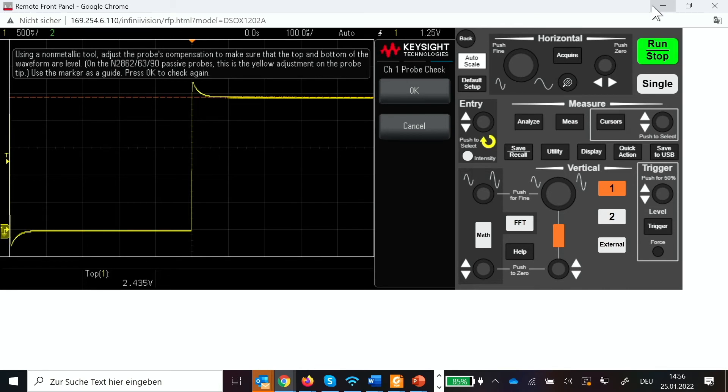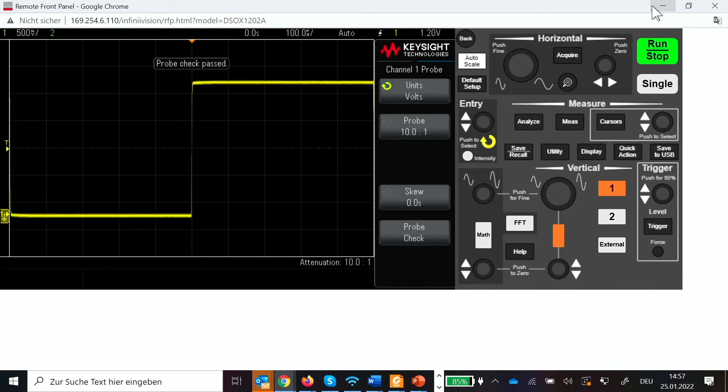You can see I can over-compensate it, under-compensate it, and if we have a straight line then we are very well compensated. Again I check, that is okay, and now we can see it's a very nice compensated signal.